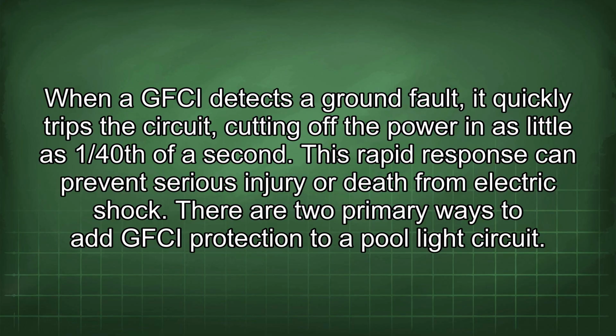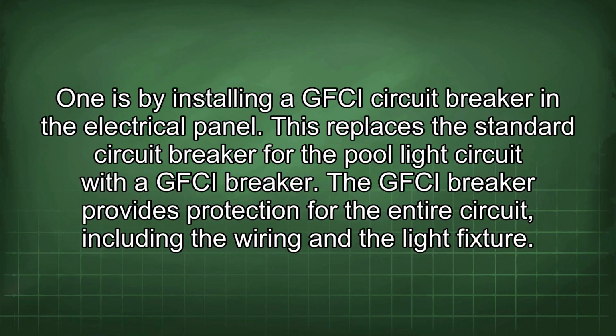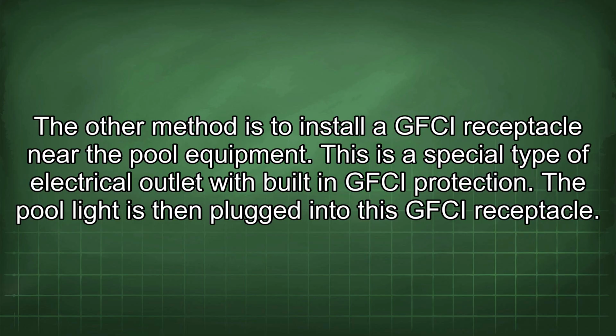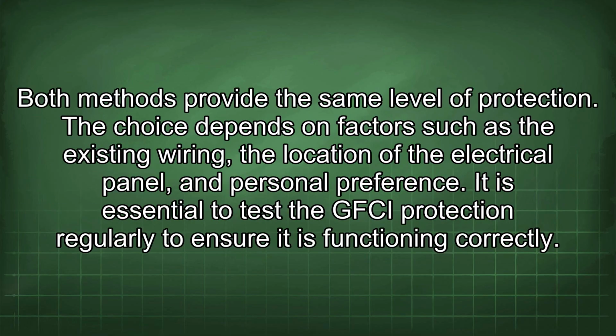There are two primary ways to add GFCI protection to a pool light circuit. One is by installing a GFCI circuit breaker in the electrical panel. This replaces the standard circuit breaker for the pool light circuit with a GFCI breaker. The GFCI breaker provides protection for the entire circuit, including the wiring and the light fixture. The other method is to install a GFCI receptacle near the pool equipment. This is a special type of electrical outlet with built-in GFCI protection. The pool light is then plugged into this GFCI receptacle. Both methods provide the same level of protection. The choice depends on factors such as the existing wiring, the location of the electrical panel, and personal preference.